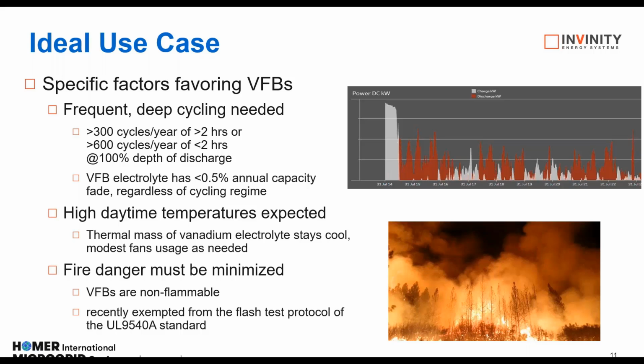That leads me to the next major indicator, which is if you're in an area where you're expecting a significant level of fire danger. As I mentioned before, vanadium flow batteries are non-flammable and were recently exempted from the UL 9540A flash test standard. What that means for customers is that they don't have to worry about taking on additional risk of a conflagration event that injures people or potentially starts yet another California wildfire because the battery couldn't handle the cooling loads.